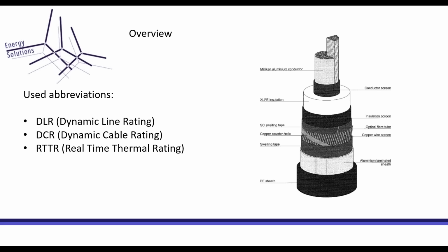And that's what in industry is also called a real-time thermal rating. So you have real-time data. You use it to calculate the thermal rating of the cable connection. So in the picture on the right, you see just an example of an underground cable, single core.